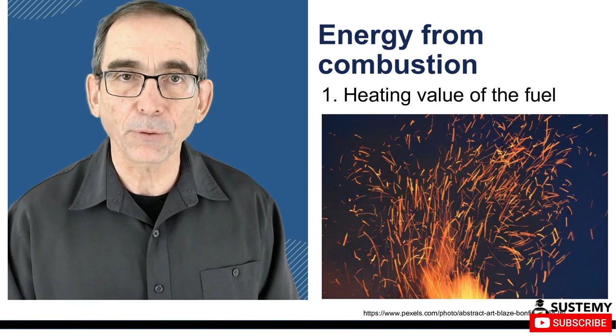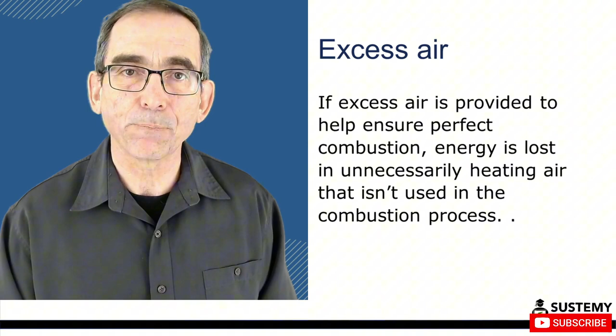When perfect combustion occurs, the byproducts of the combustion process are carbon dioxide and water. With imperfect combustion, other products such as carbon monoxide and nitrous oxides might form due to insufficient oxygen. On the other hand, if excess air is provided to ensure perfect combustion, energy is lost in unnecessarily heating the air that goes through the burner but isn't used in combustion.